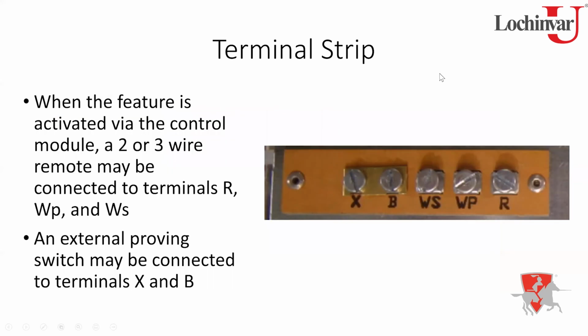Now, the terminal strip, you've got your first two terminals there, X and B with the jumper. This is where you're going to wire in any kind of remote safeties. Again, like I said, the external flow switch, if you wanted to add it, or some other pressure switches, or some other device that might need to be added, that's where it's going to go. The other three terminals, your R, your WP, and your WS, will coincide with either a 2 or a 3 wire remote device. To use those, we will have to do a little programming in the control. We'll talk about that just momentarily as far as their functions, all right?